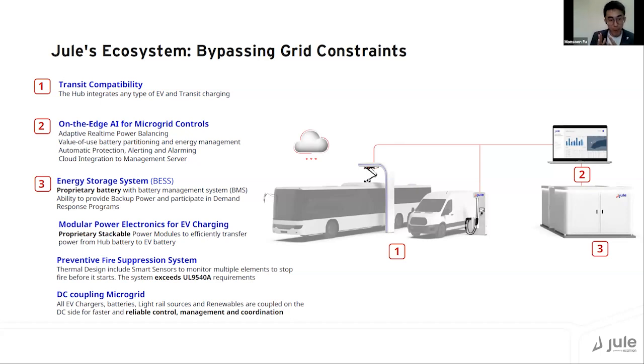This makes the application binary, meaning that to prevent backfeed, they rely on a backfeed preventer. If the net energy into the grid surpasses a threshold, the entire site will be cut off. Whereas in our case, we aggregate everything on a DC bus designed by us, and we use the PCS as an active control gateway for the interaction between the grid and the DC microgrid.